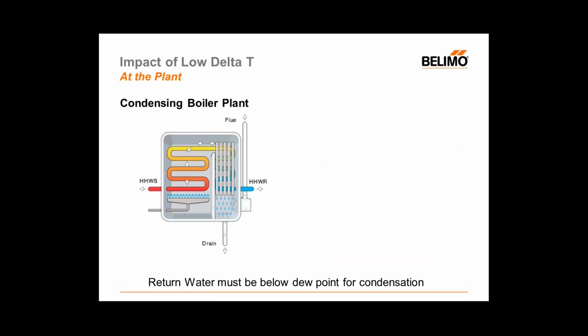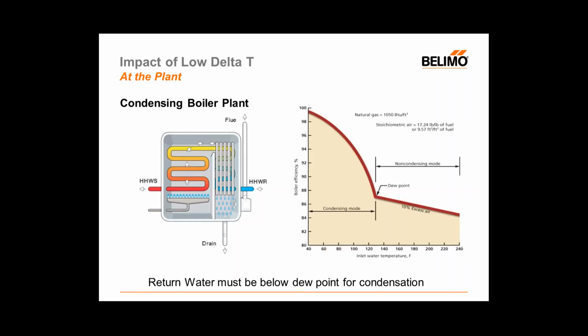If we're talking about heating, the biggest net benefit from a plant standpoint of delta T improvement would be on more advanced style condensing boilers. So a condensing boiler works by preheating the return water by creating a condensing process of the flue gas over the relatively cool water that's returning from your coil. In a traditional boiler, we would just have the second stage fire heating area, and we would not preheat the water. So the big function for condensing boilers is that the return water needs to be cool enough to create the condensation process in the first stage preheat. And so the lower the return water is, the higher the efficiency will be of your condensing boiler.